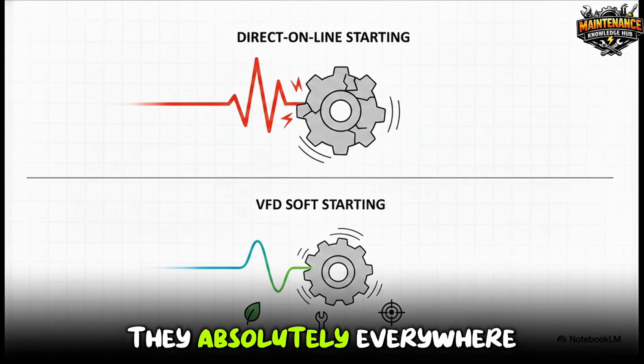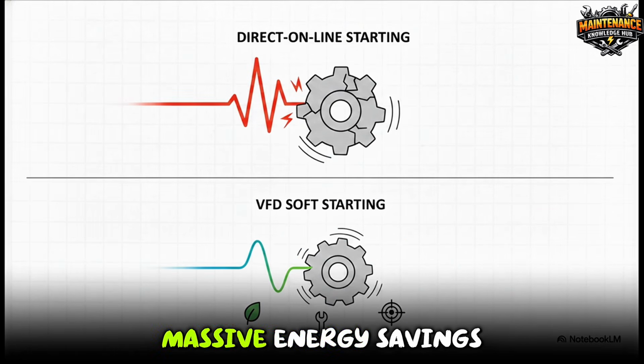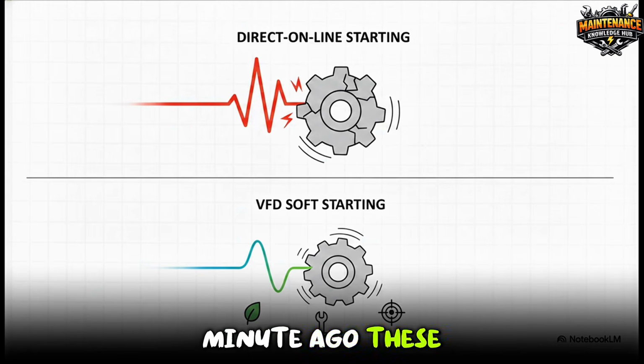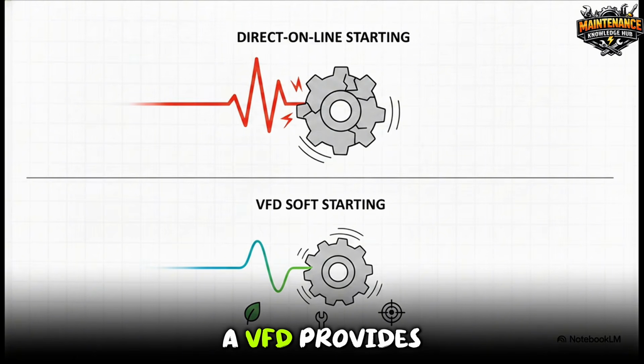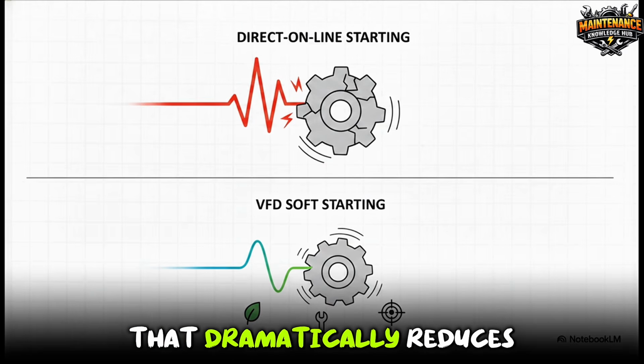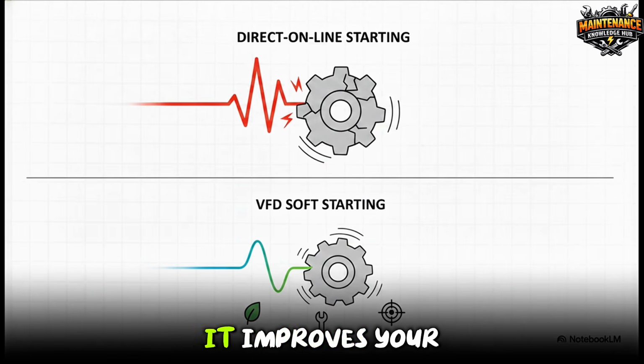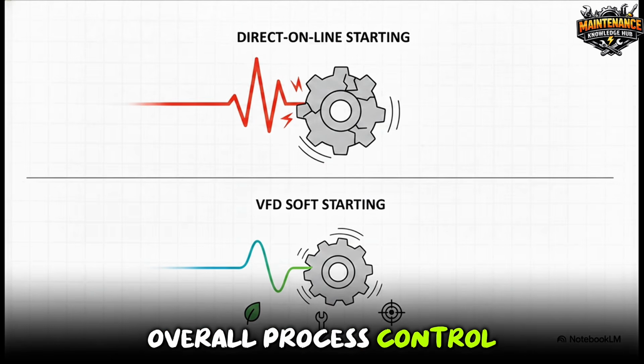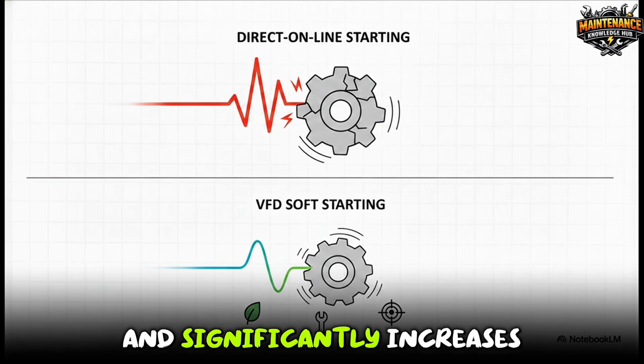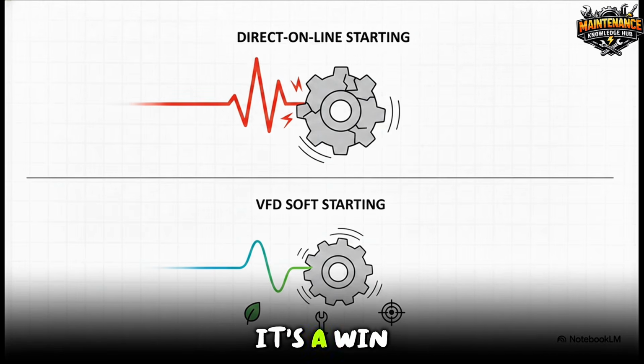So why are they absolutely everywhere? Well, beyond those massive energy savings we teased a minute ago, these devices drastically reduce mechanical wear and tear. Instead of just slamming a motor on at full speed right out of the gate, a VFD provides a really smooth motor starting and a soft stopping process. That dramatically reduces mechanical stress, it improves your overall process control, lowers maintenance costs, and significantly increases the lifespan of the equipment. It's a win-win.